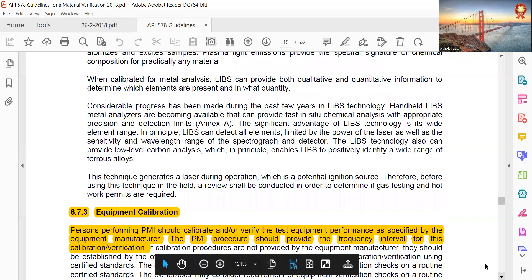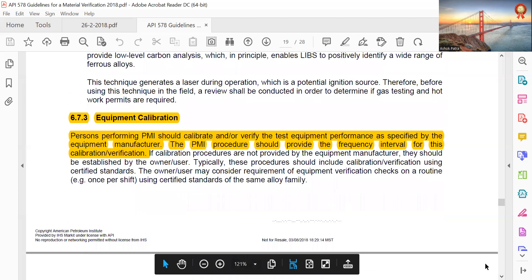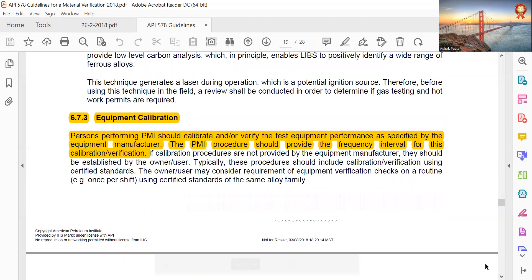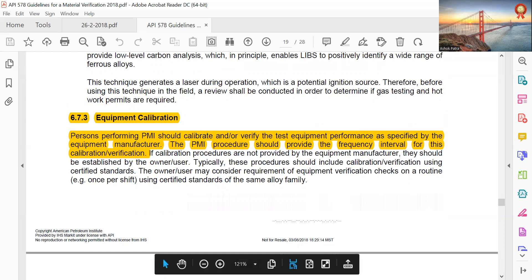Equipment calibration: the person performing PMI should calibrate and/or verify test equipment performance as specified by the equipment manufacturer. The PMI procedure should provide the frequency and interval for calibration verification.